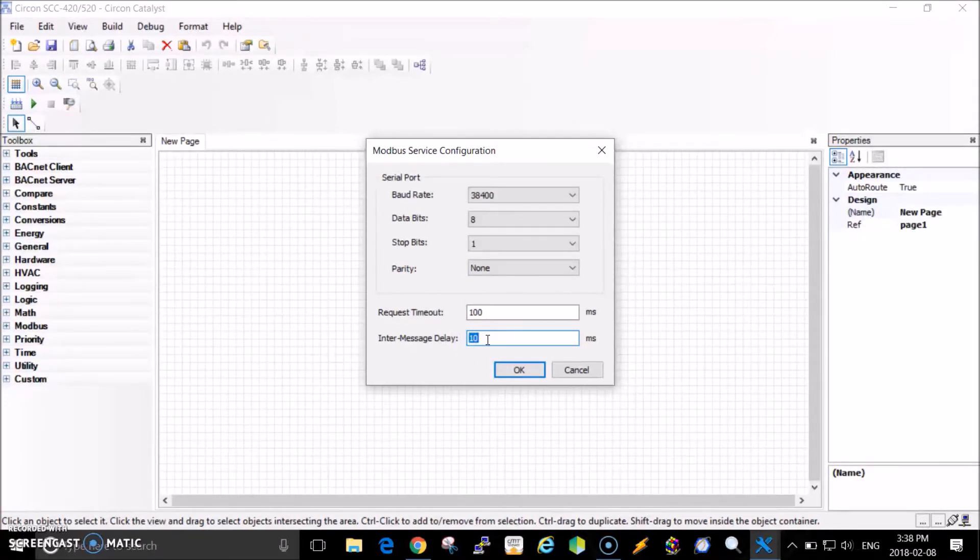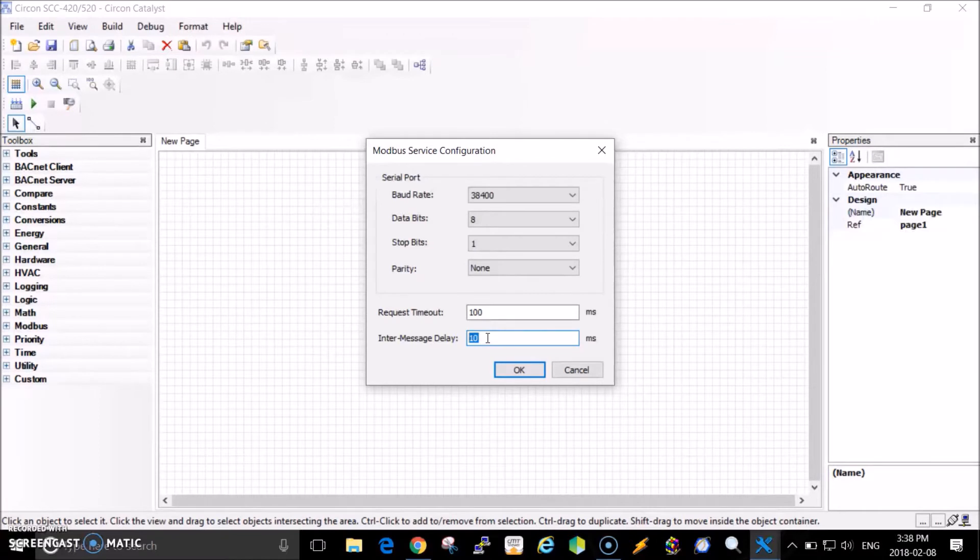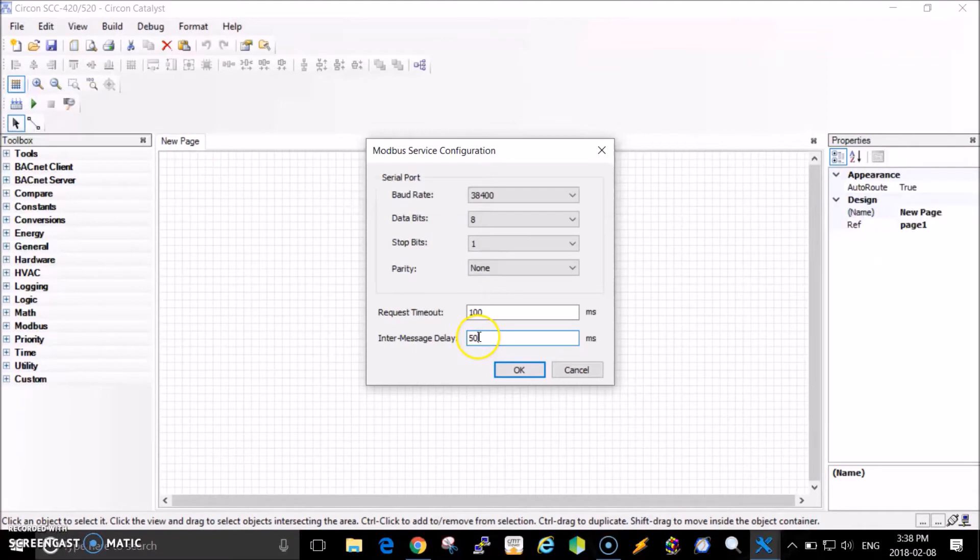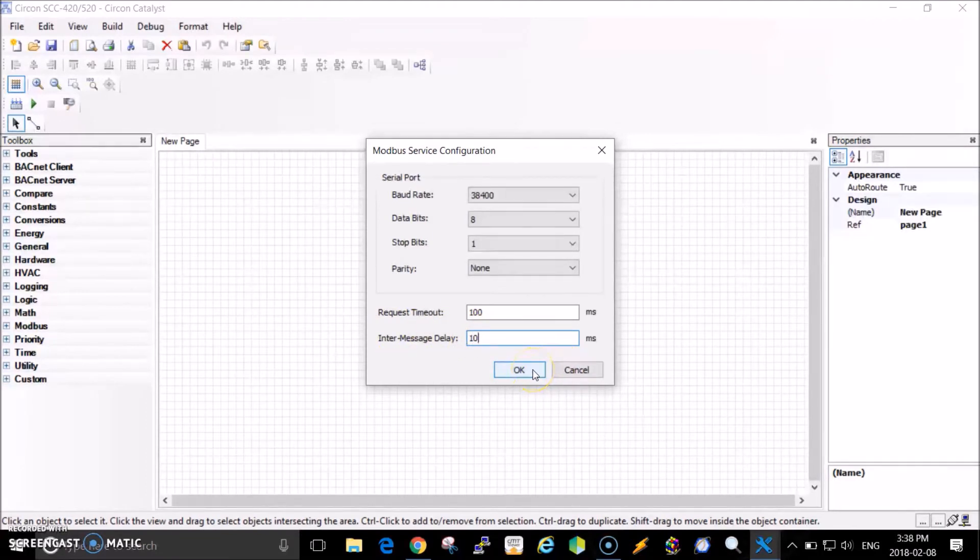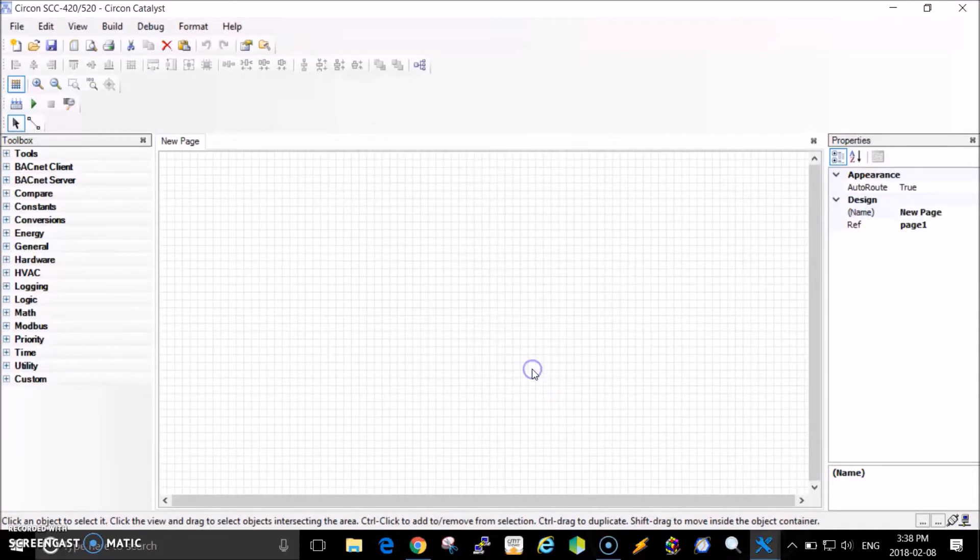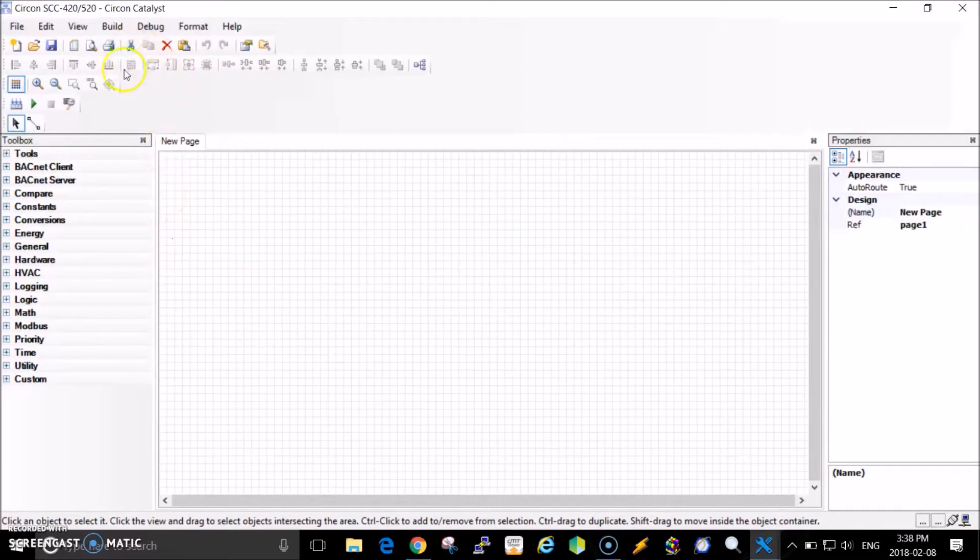Sometimes you have to increase the inter-message delay. When you connect to a real compressor, you'll see if you're missing data or if data is intermittent. After verifying the wiring is correct, you can increase this maybe to 50 milliseconds, or leave it at 10 milliseconds if everything's fine. Let's leave it at 10 for now.